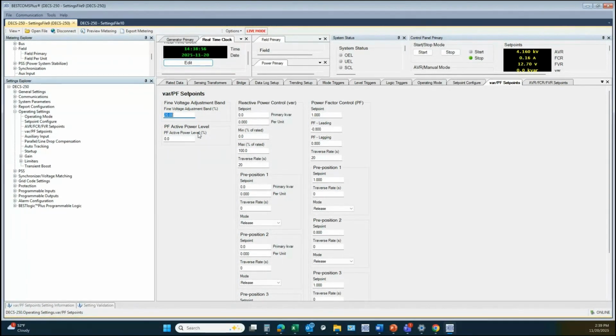Power factor active level is how much real power needs to be present on the machine before you allow power factor control to become active. It can be very difficult to determine the precise power factor level if there's hardly any power present. So a lot of applications will leave that at 0%. Some will bump that up to as much as 5% or so.